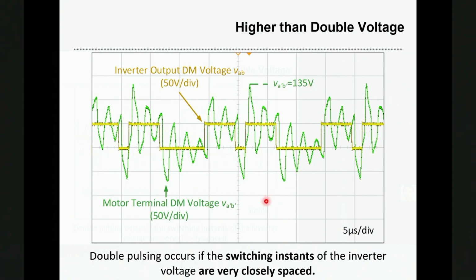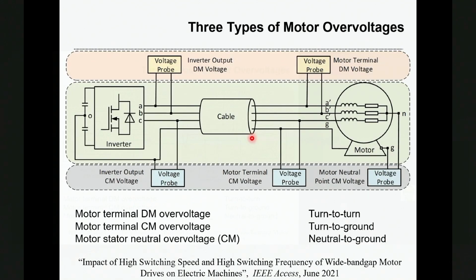This happens because the switching instants of the inverter output voltage are very closely spaced. We call this the double pulsing effect. Basically, the two pulses are too close to each other. This happens when you have a high switching frequency and also the modulation index is high. So I will summarize, there are 3 types of motor over voltages. At the motor terminal, there are 2 types of over voltage. That is a differential mode over voltage, that is the phase-to-phase or the line voltage. And there is also the motor terminal common mode over voltage, that is the phase to ground over voltage.